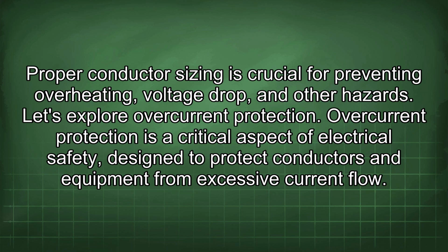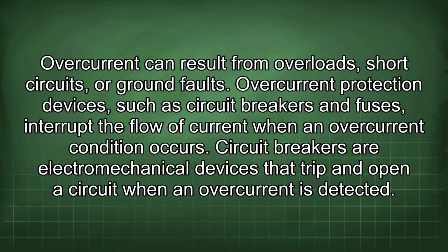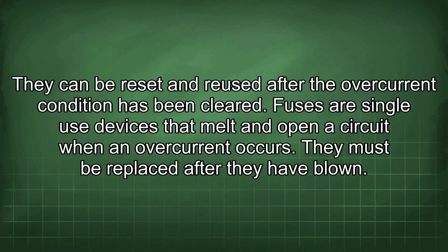Let's explore overcurrent protection. Overcurrent protection is a critical aspect of electrical safety, designed to protect conductors and equipment from excessive current flow. Overcurrent can result from overloads, short circuits, or ground faults. Overcurrent protection devices, such as circuit breakers and fuses, interrupt the flow of current when an overcurrent condition occurs. Circuit breakers are electromechanical devices that trip and open a circuit when an overcurrent is detected. They can be reset and reused after the overcurrent condition has been cleared.